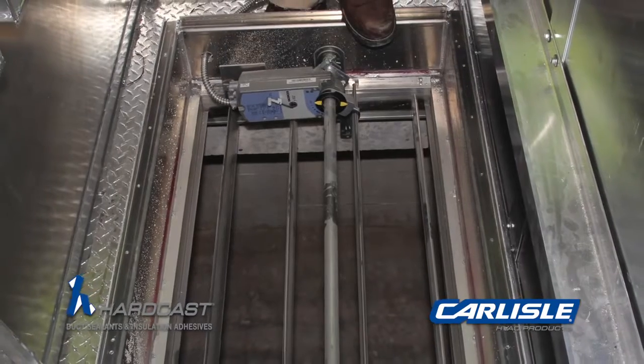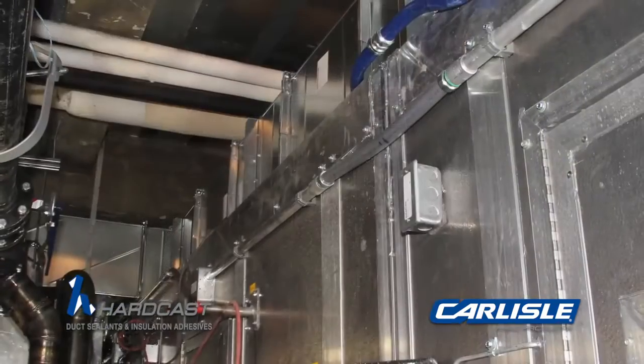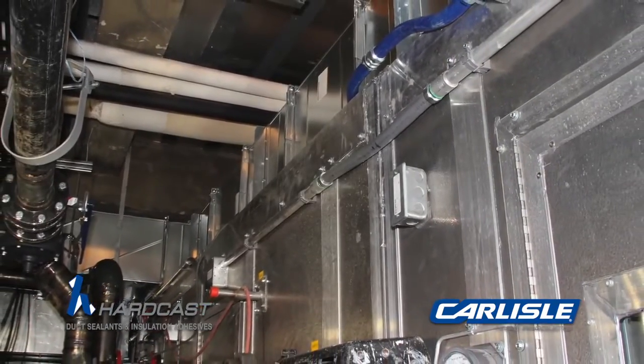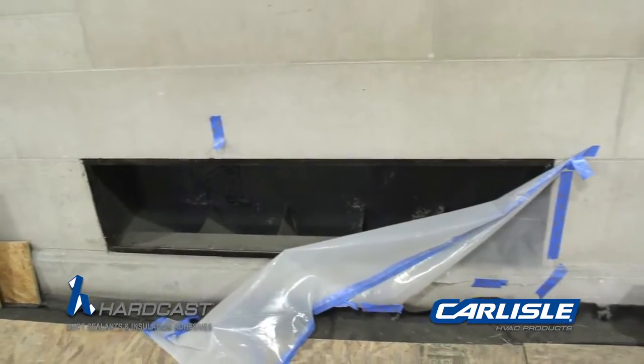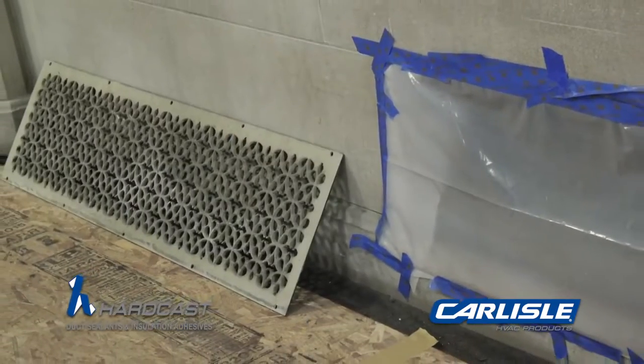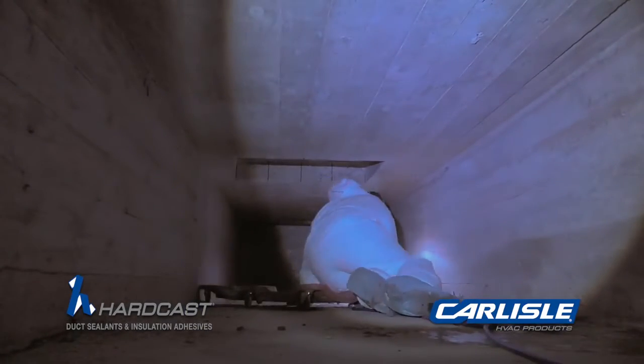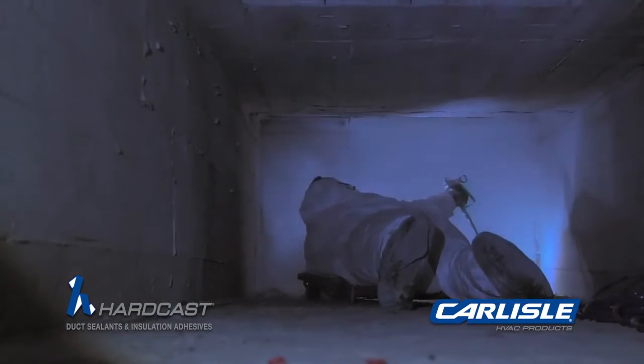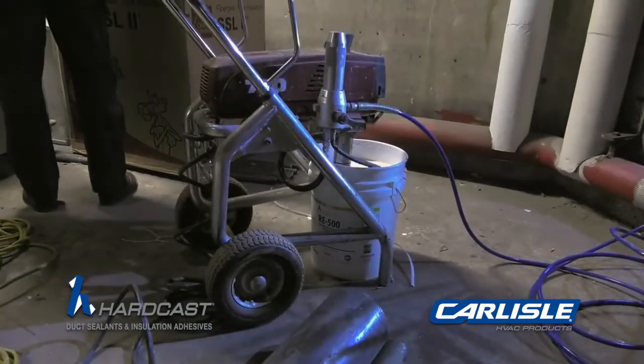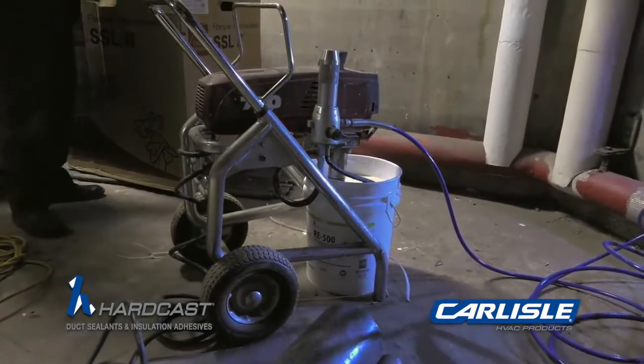Currently, we are at Duke University Chapel cleaning the existing ductwork. The scope of the project, as far as the heating and air conditioning was concerned, was that they were replacing the existing air handling units. Our scope of work was to clean all the ductwork and grills that remained. They expanded that to include about 100 feet of underground fresh air duct that had originally been taken out of service. They decided they were going to put it back in service, and they wanted to coat it. We proposed the RE500 system from Carlisle Hardcast.